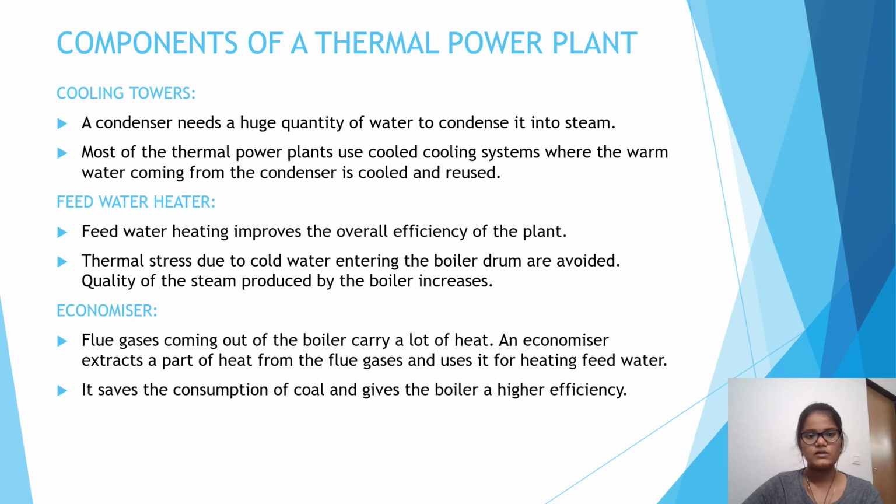Economizer. Flue gases coming out of the boiler carry a lot of heat. An economizer extracts a part of heat from the flue gases and uses it for heating feed water. It saves the consumption of coal and gives the boiler a higher efficiency.